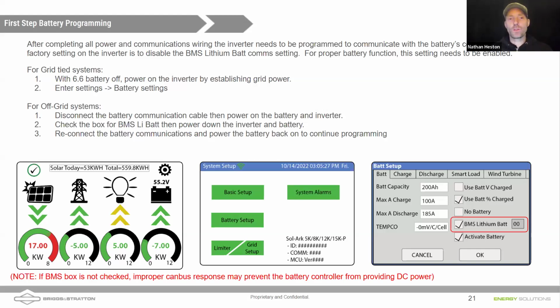If we have no other power source, like a generator, maybe we've got an off-grid system, we don't have a generator to start up and get the inverter powered up and tell it to communicate on a CAN bus channel, what we can do is we can disconnect the battery cable so that the battery controller thinks it's running in open loop mode. And then we can power on the inverter off of the battery power. And then we'll go in and we'll check that box for BMS lithium battery in the same way that we would with using grid power. Click OK, and then we'll shut the inverter down. We'll shut the battery down.